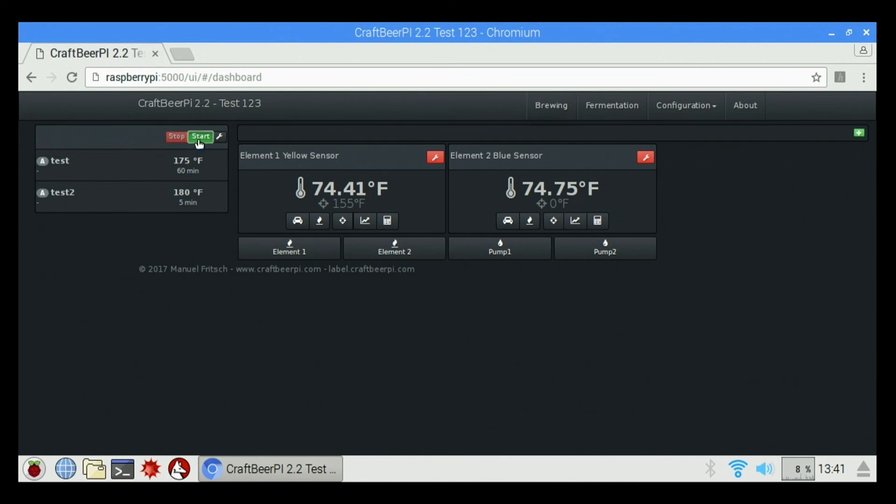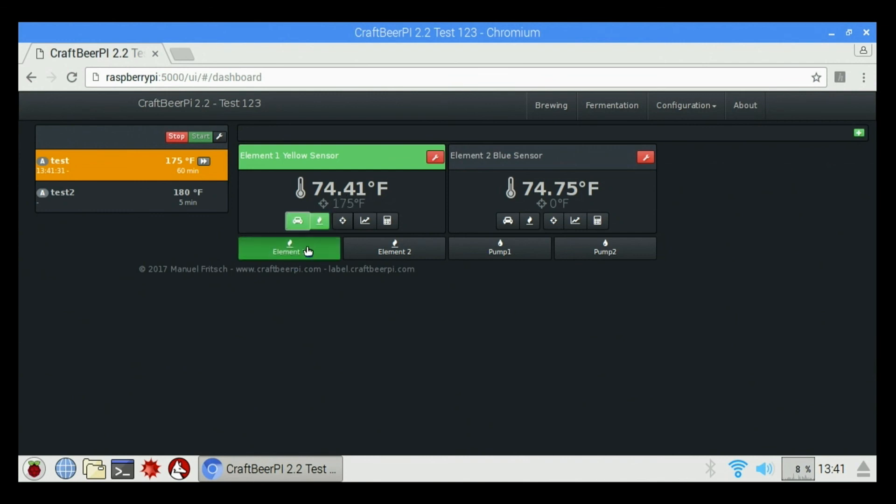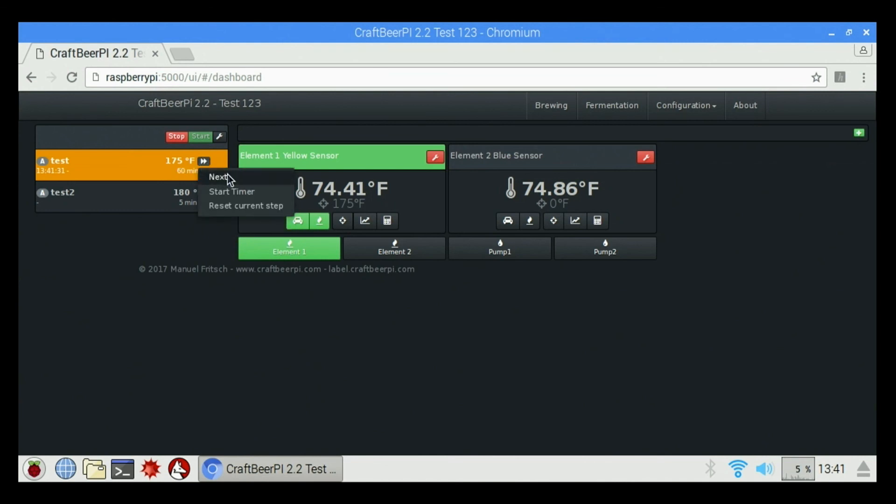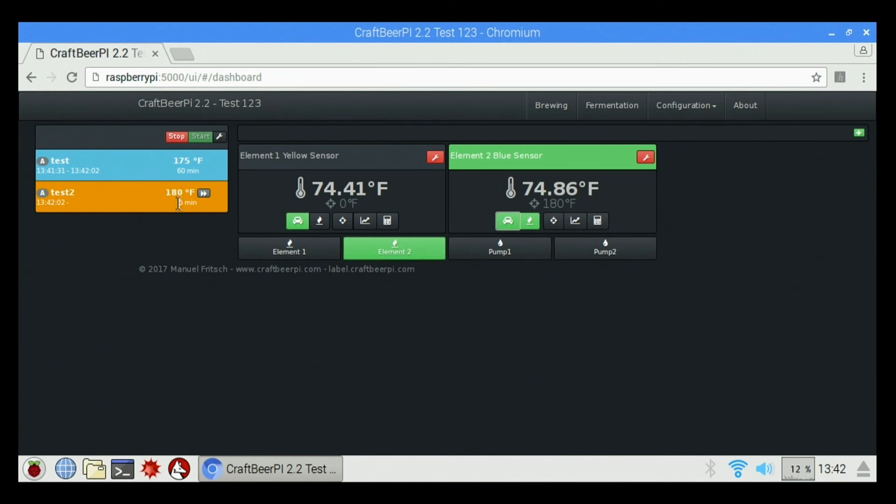And if I hit start, it's going to go to element one sensor and it's not going to do anything until I click this auto button. Once I click the auto button, it's set my temperature and it turned on my element. Once it reaches 175, it's actually going to keep it there for 60 minutes. And then it'll start the timer as soon as it reaches the temperature. So you can also skip the step by clicking this arrow and go to next step. And it flipped it from the yellow to the blue. I don't have my auto on, so it's not going to do anything. So I click on my auto and it'll start that process as well. See my element two is on.